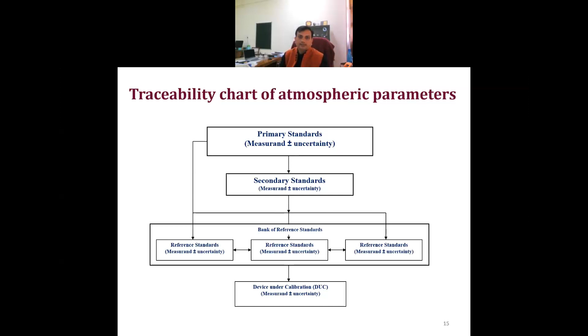This is the traceability chart for atmospheric parameters. We have a primary standard. On the basis of the primary standard, we provide a secondary standard and calculate uncertainty. The secondary standard again has reference standards, and finally this helps to calibrate the devices. You have seen this traceability chart many times, maybe as presented by our other colleagues. Besides this, we have various types of instruments used for trace gas measurements. For methane, we measure through a gas chromatograph and gas analyzer.